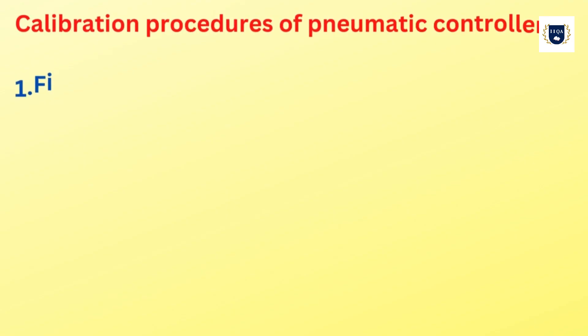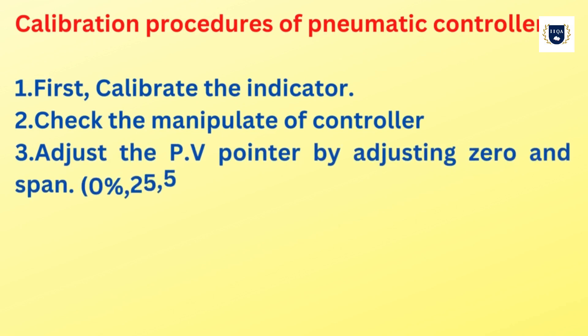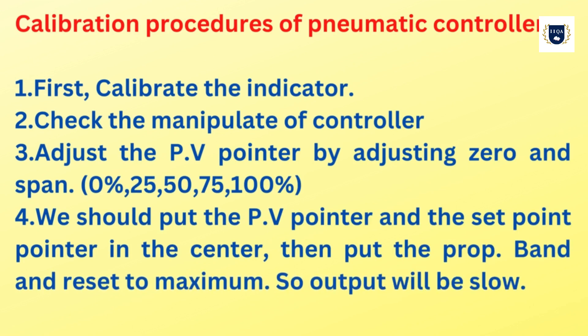Calibration procedures of pneumatic controller. First, calibrate the indicator. Check the manipulate of the controller. Adjust the PV pointer by adjusting zero and span: 0%, 25%, 50%, 75%, 100%. Put the PV pointer and the set point pointer in the center, then put the proportional band and reset to maximum, so output will be slow.